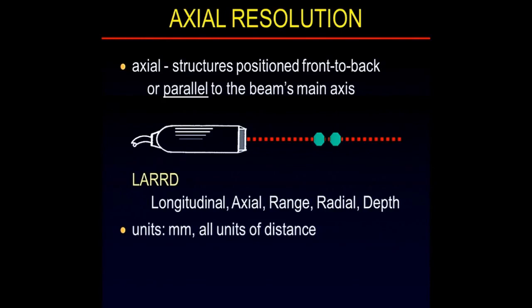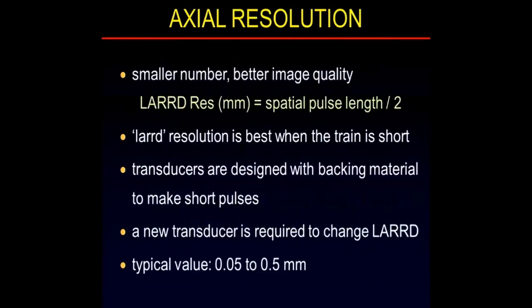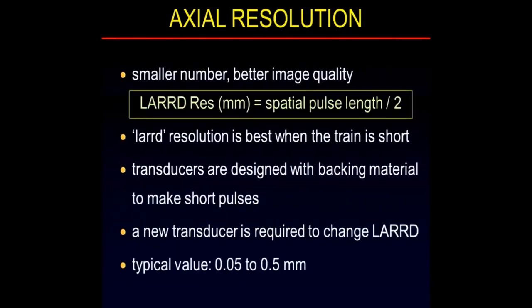The question that's answered is, if two structures are close together, one in front of the other, do I see them as two separate blips? That would be good. Or do I see them as a blob? So axial resolution tells us how accurate our picture is when reflectors are one in front of the other. It has units of distance, and it is equal to our old friend, the spatial pulse length divided by 2, which means the shorter the pulse, the lower the number, the better the picture.